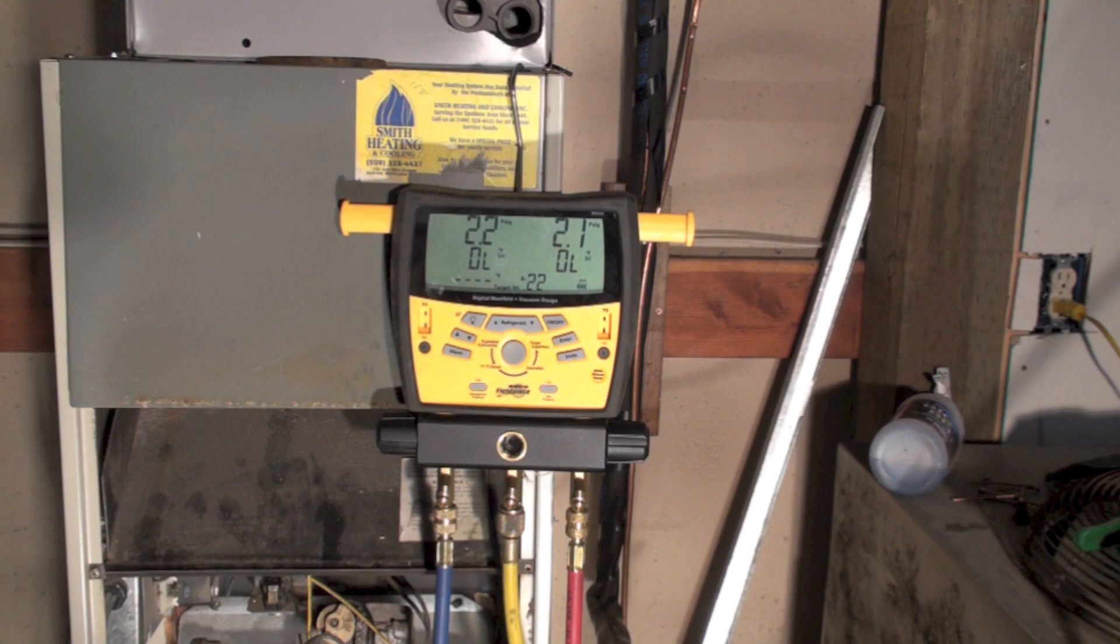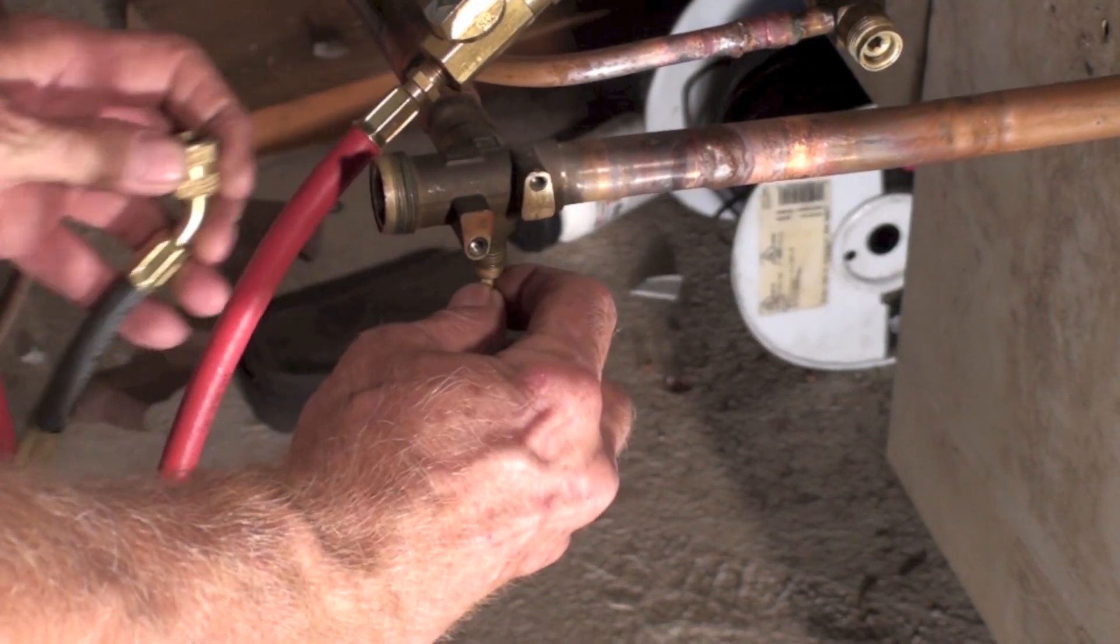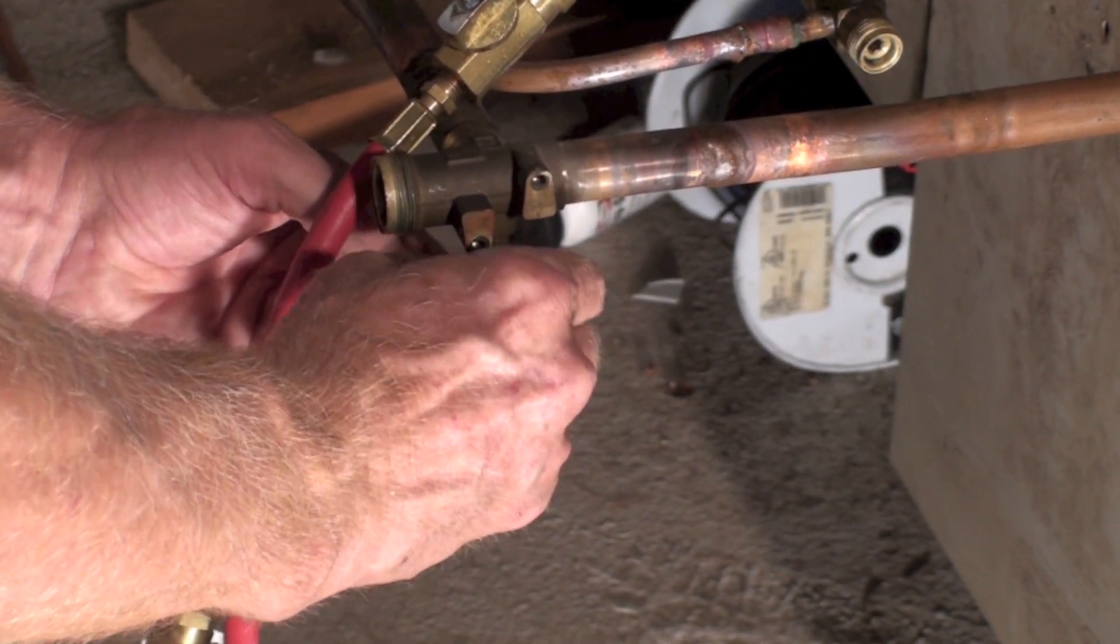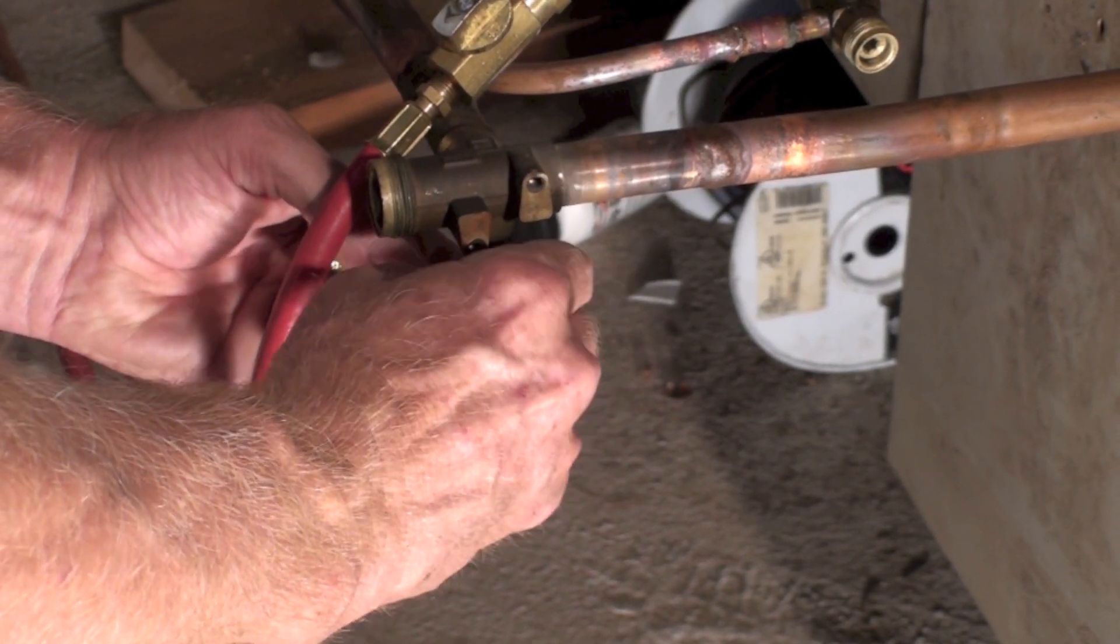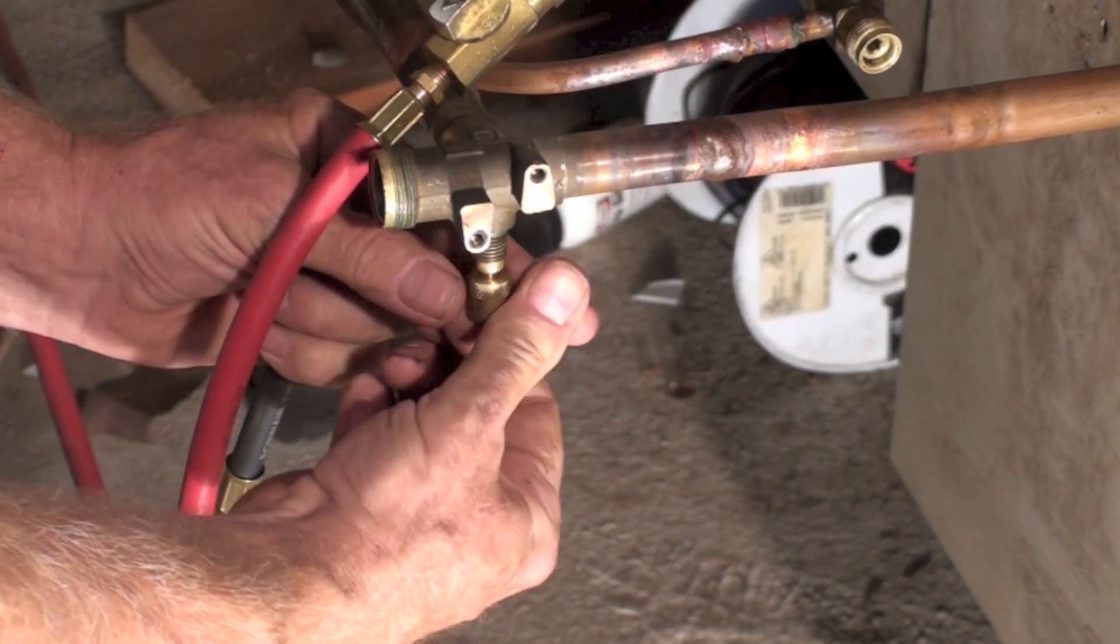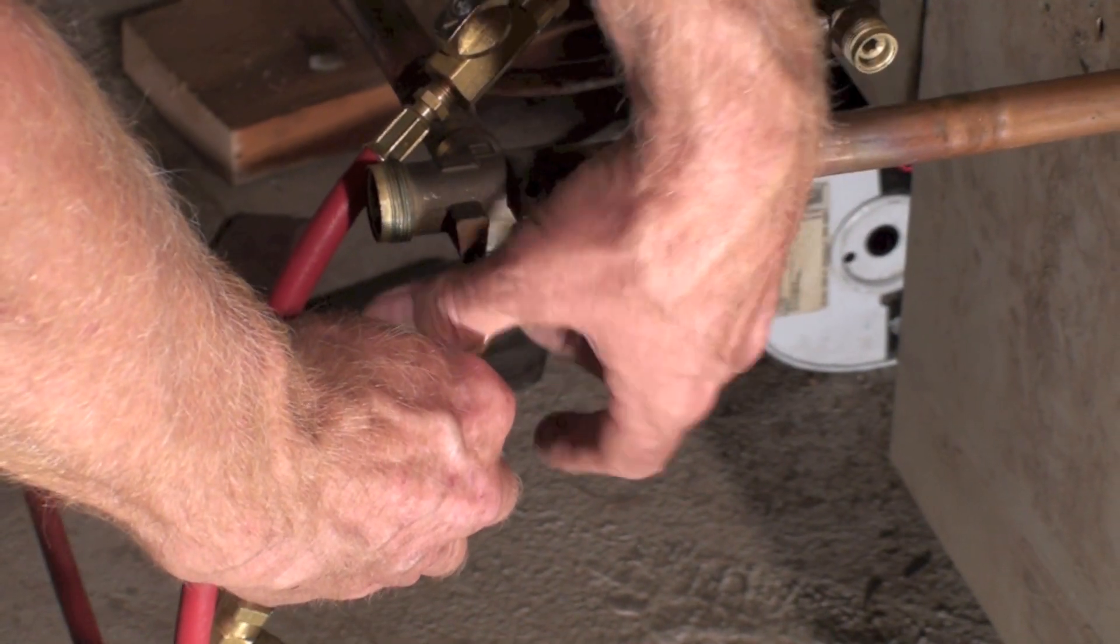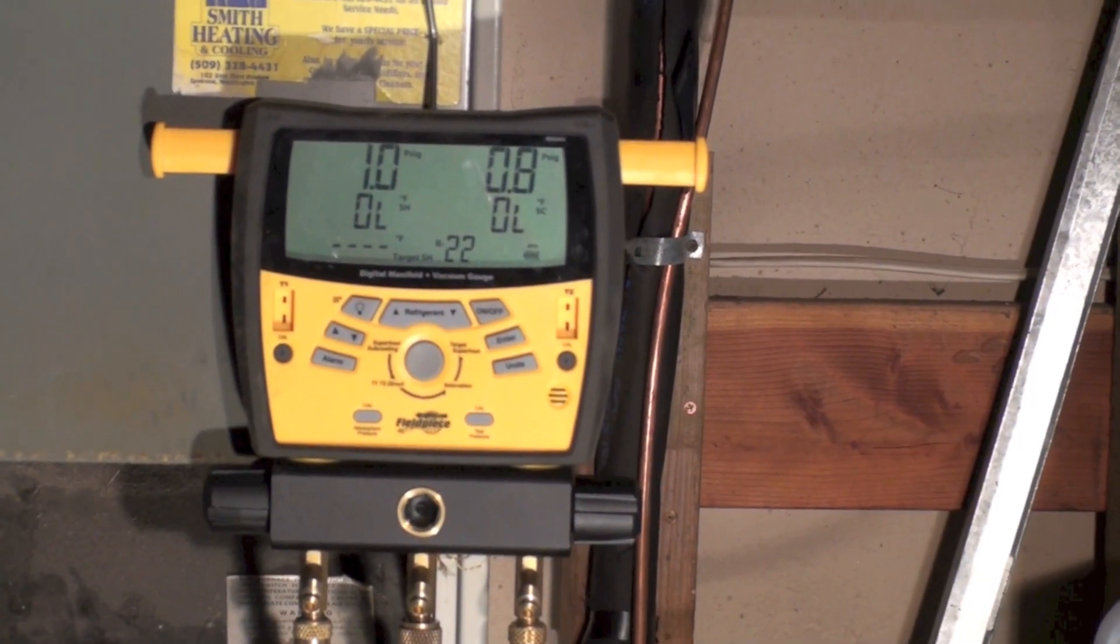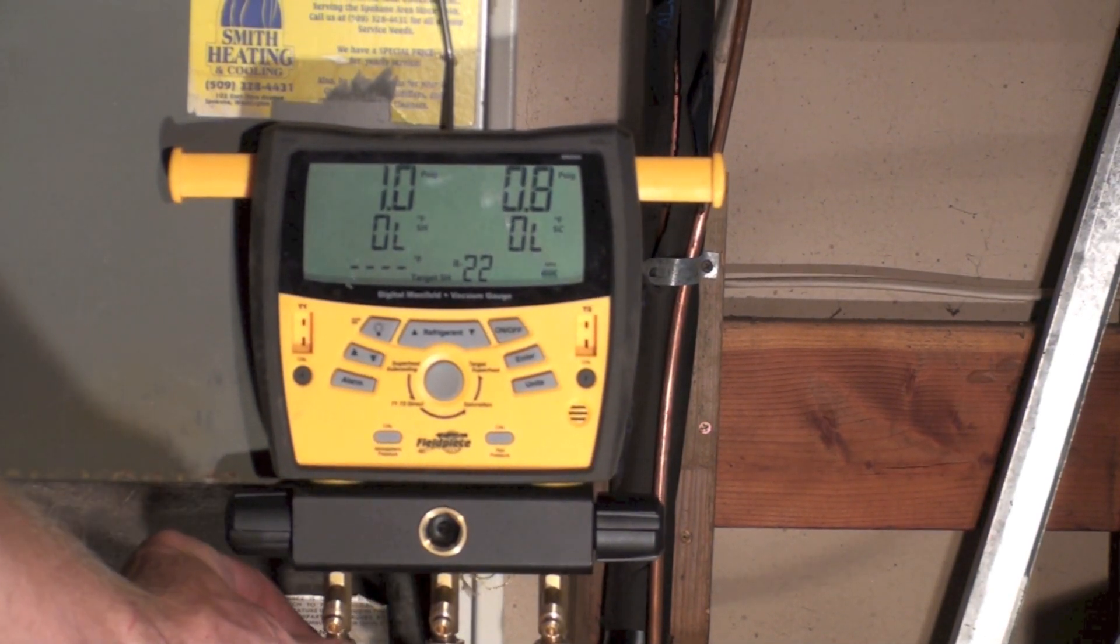Okay, then I'm going to do it with the other one the same way. And again, I'm going to bleed the air out of the line. And that's replacing the Schraders after evacuation.